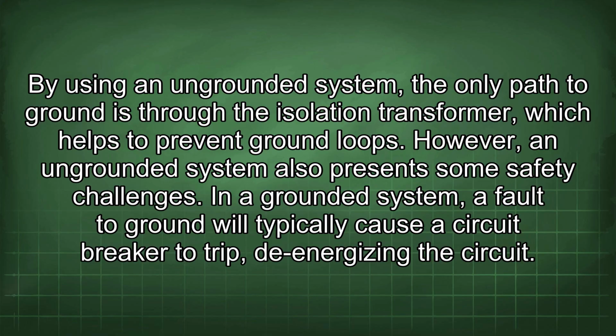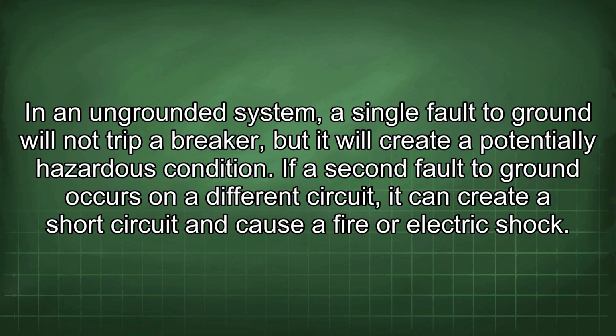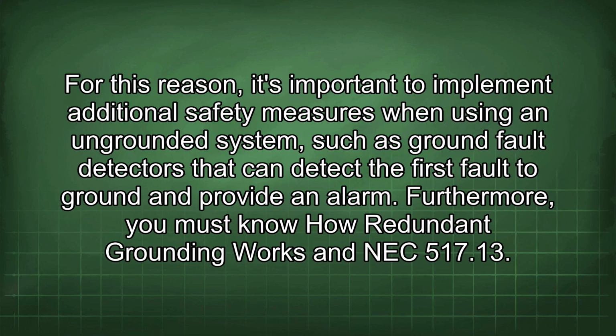In a grounded system, a fault to ground will typically cause a circuit breaker to trip, de-energizing the circuit. In an ungrounded system, a single fault to ground will not trip a breaker, but it will create a potentially hazardous condition. If a second fault to ground occurs on a different circuit, it can create a short circuit and cause a fire or electric shock. For this reason, it's important to implement additional safety measures when using an ungrounded system, such as ground fault detectors that can detect the first fault to ground and provide an alarm.